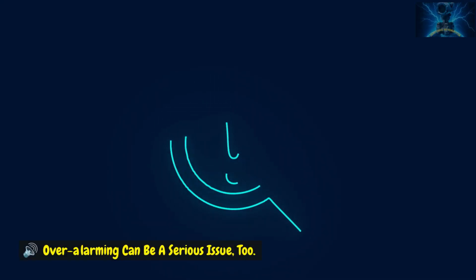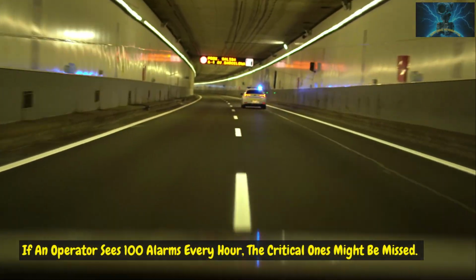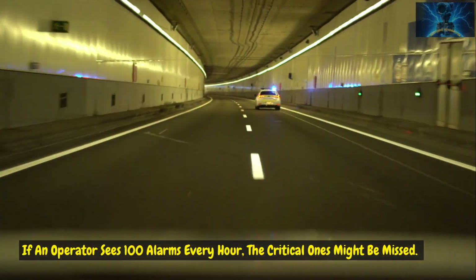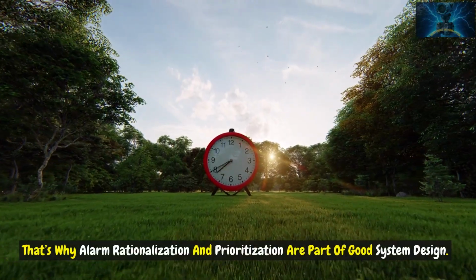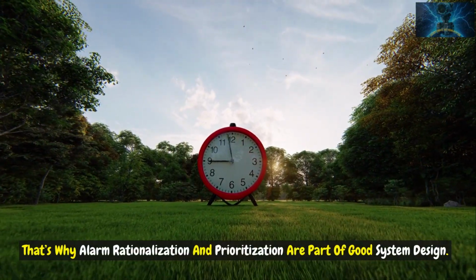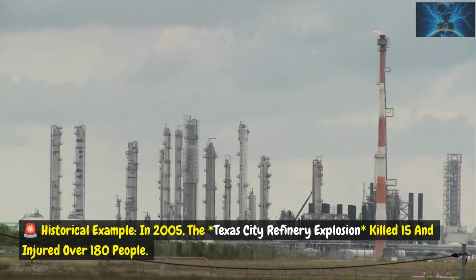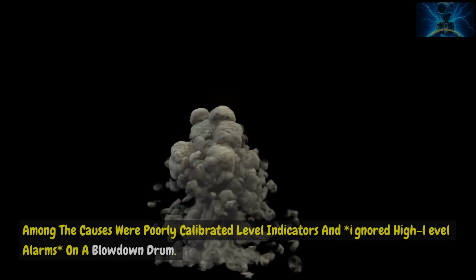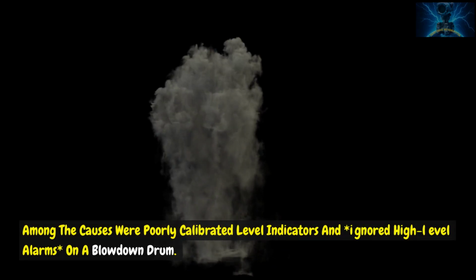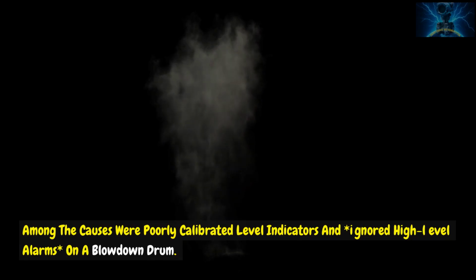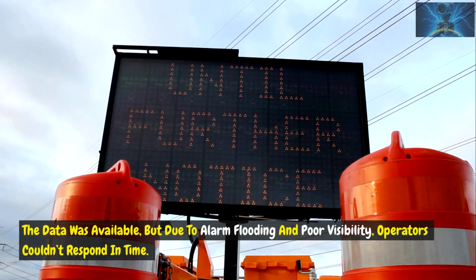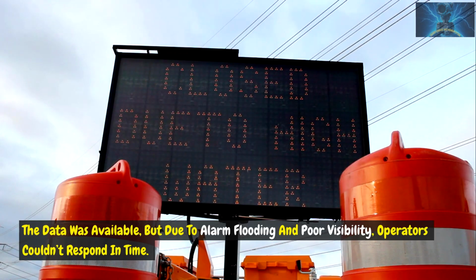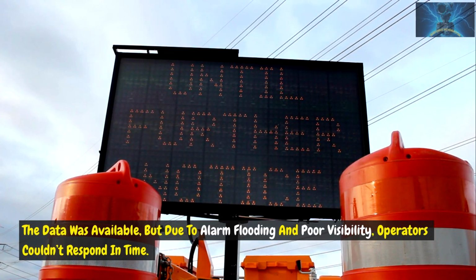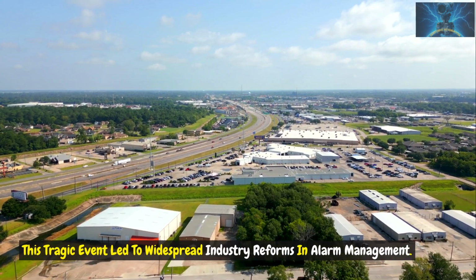Over-alarming can be a serious issue too. If an operator sees 100 alarms every hour, the critical ones might be missed. That's why alarm rationalization and prioritization are part of good system design. Historical example: in 2005, the Texas City Refinery explosion killed 15 and injured over 180 people. Among the causes were poorly calibrated level indicators and ignored high-level alarms on a blowdown drum. The data was available, but due to alarm flooding and poor visibility, operators couldn't respond in time. This tragic event led to widespread industry reforms in alarm management.